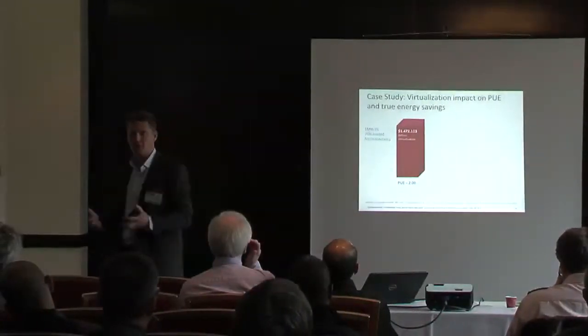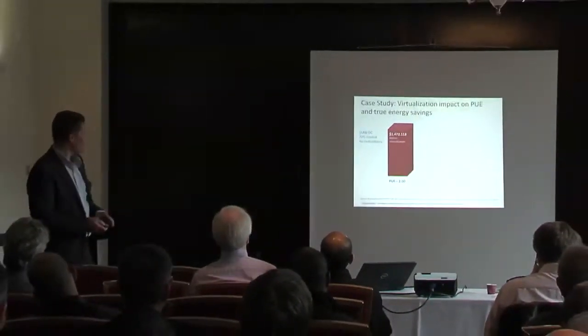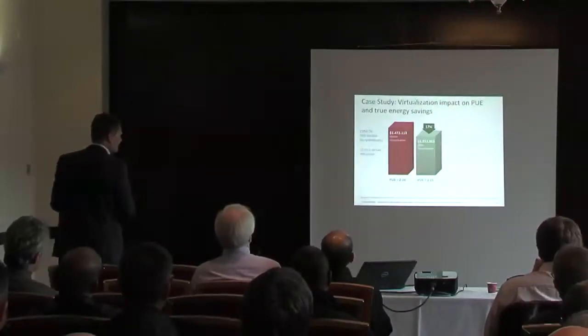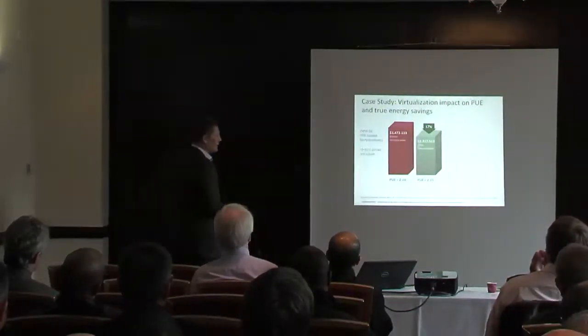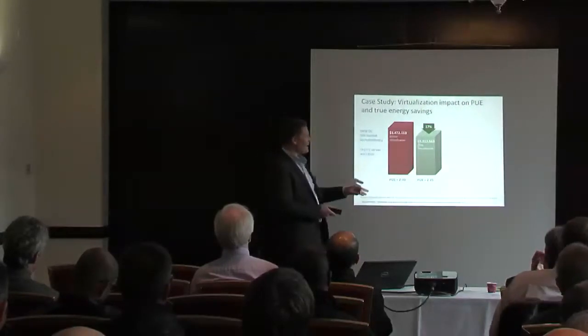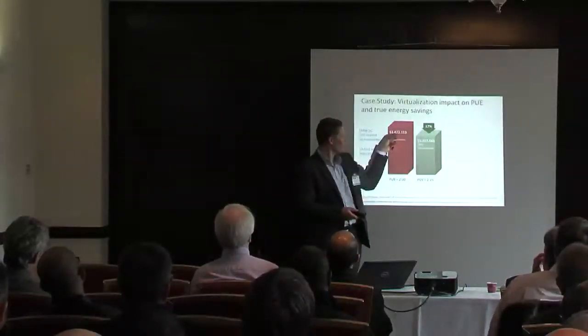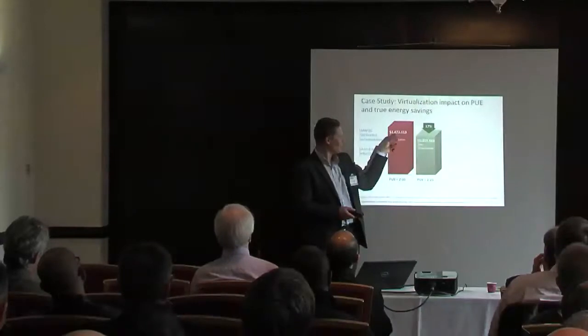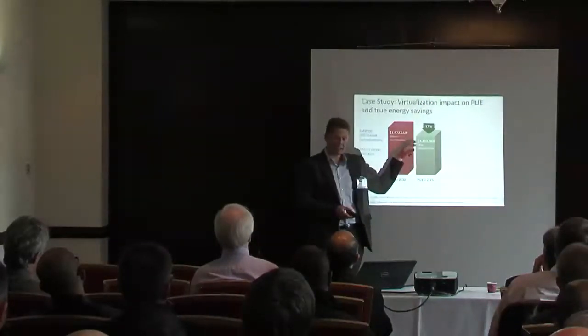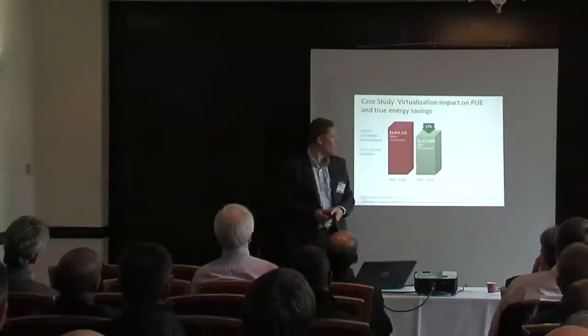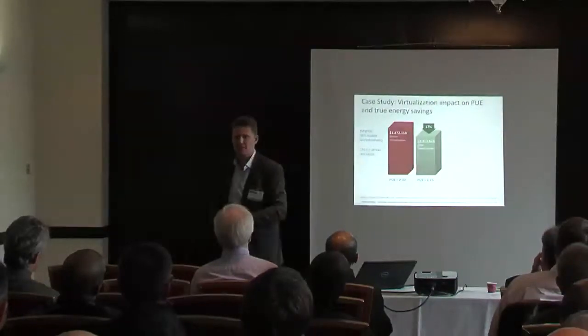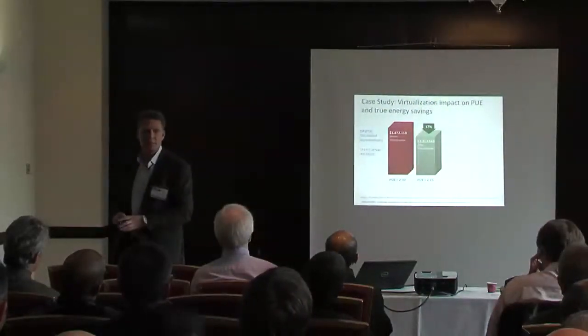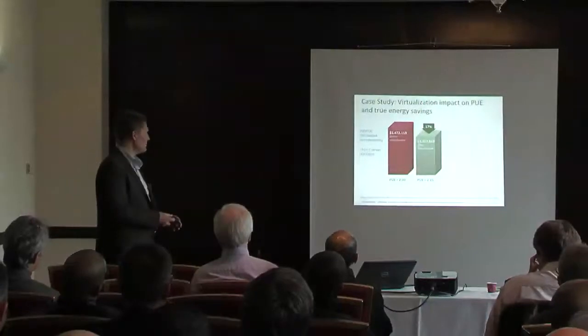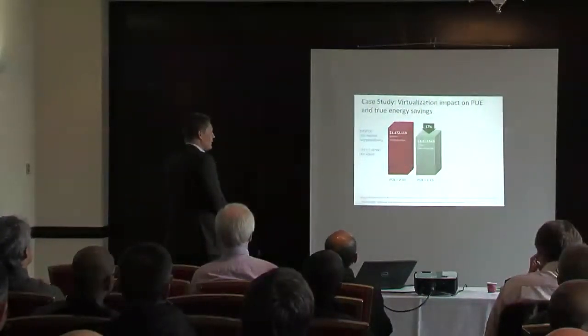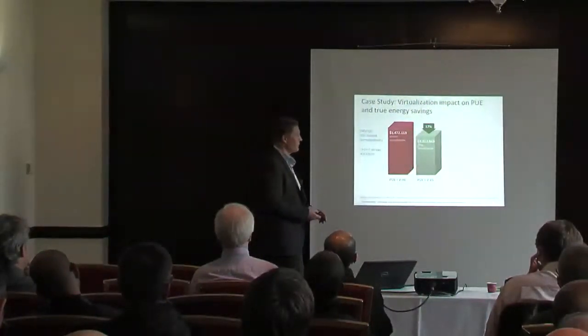Now we want to start virtualizing in this data center, and we actually virtualize with a very aggressive 10 to 1 server reduction. What that gives us is we went from just below 1.5 million US in pure energy cost per year down to 1.2, a 17% reduction. Fantastic, so we did good, we reduced energy by almost $300,000 for a year.